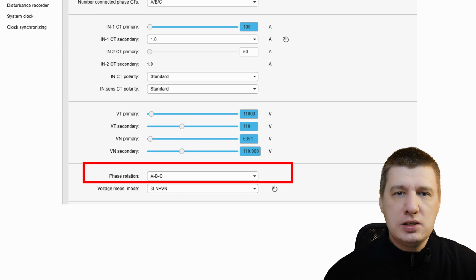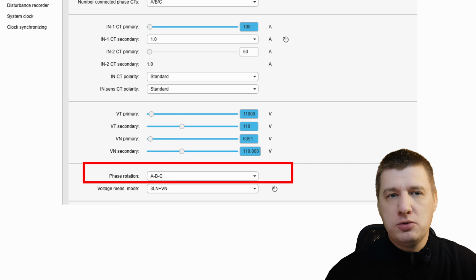You can configure this in eSetup Pro under scaling. To verify it on site, the source recommends using the phase rotation meter during the primary injection test. You should also check the HMI to ensure the voltage angles are displayed according to sequence. In short, match the relay to your system reality. If the wires say ACB, then the relay must say 1, 3, 2.